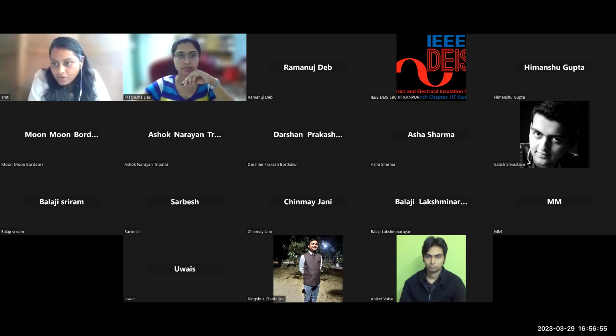Aniket asked, how can we accurately characterize insulation state properly in the presence of dynamic factors such as moisture migration and the influence of low frequency noise in dielectric response analysis such as PDC? As you are probably aware, moisture migration can be monitored through dielectric response or frequency response methods, but there are other methods available as well. One of the most famous, although a bit indirect, is the KFT, Karl Fischer titration, governed by, I think, the IEC 60814 standard. You can read about how to do it there.